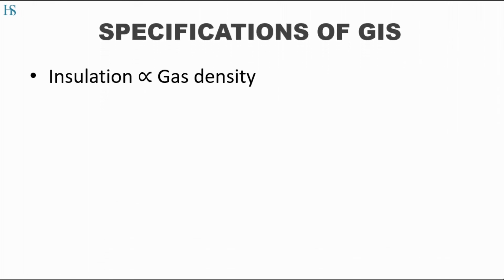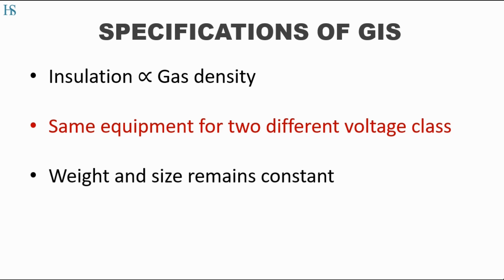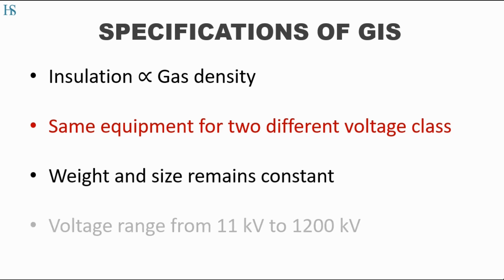Since the insulation is directly proportional to the gas density, the desired voltage class is achieved just by increasing or decreasing the gas density. Due to these flexibilities, some manufacturers offer the same equipment for two different voltage classes, keeping the weight and size of the instrument the same. GIS are available in a voltage range of 11kV to 1200kV.